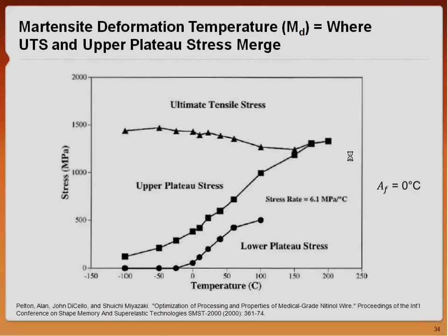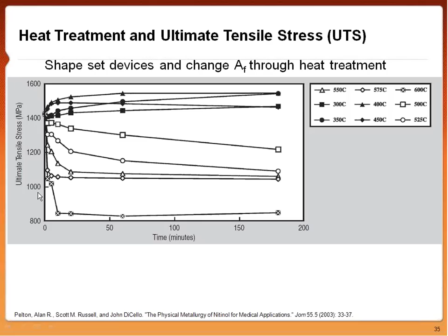So again, we want to change things to our advantage. We can heat treat or shape set our devices. When we do that, we can get detrimental effects in our ultimate tensile strength of our material. It's basically a trade-off. Higher temperatures will give you a better shape. However, the better shape will have a detriment in the ultimate tensile strength of the material. So at 600 degrees Celsius, shape set time is going to give you a good shape. However, the more time you do it, it's going to seriously decrease the ultimate tensile strength of your material.